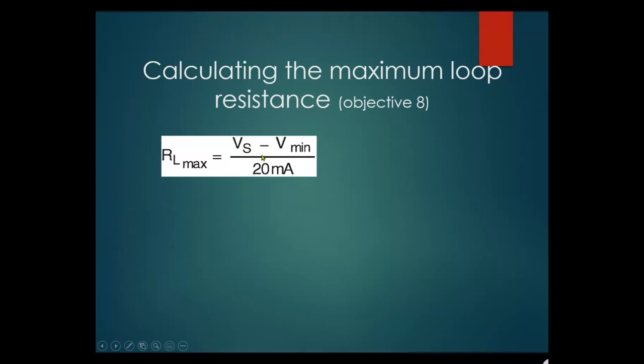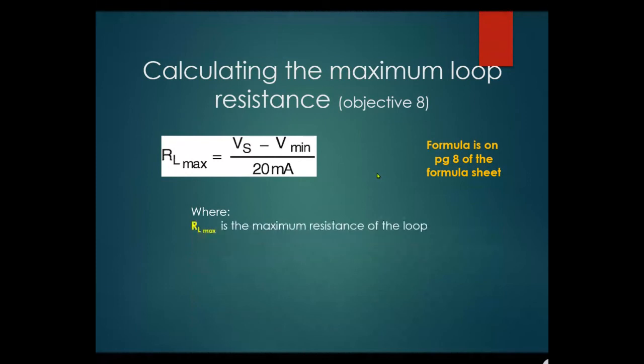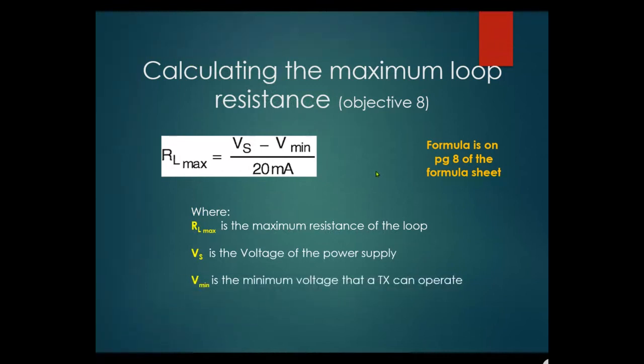The formula is on page 8 of the formula sheet. RL is the maximum loop resistance, VS is the voltage supply, and V-minimum is the minimum voltage at which the transmitter can operate. With 4 to 20mA going through the loop with multiple 250 ohm drops, you need enough voltage to supply the transmitter as well as the loop. If there isn't enough, it will not work — you'll see this demonstrated in one of your labs.